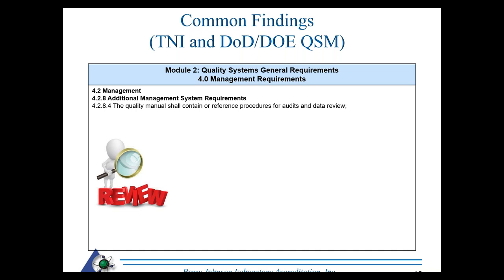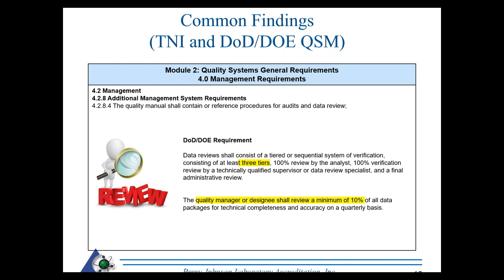Under 4.2 management, the quality manual must contain information on data review, audits, and procedures for those activities. DOD/DOE has additional requirements for a three-tier data review, specifying what each tier shall contain and the percentage of review for each tier. It also requires the quality manager or designee to review at least 10% of data packages. Labs transitioning to DOD/DOE often miss these tiered and quality manager requirements.